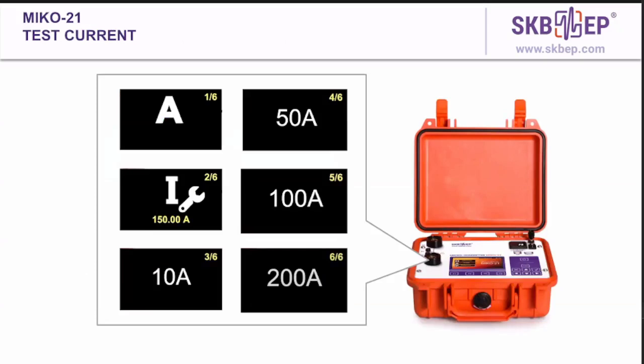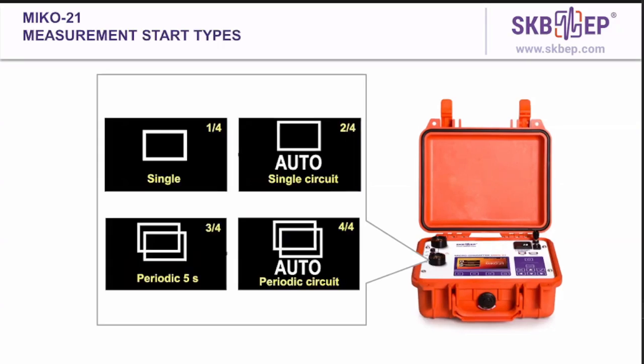In the settings, here it's about the adjustable amperage mode. In the settings, you can choose the current you want. First of all, you can set the automatic mode for selecting the test amperage. You can set it manually in the range from 1 up to 200 ampere with a step of 1 ampere. And you can also select from a number of specified values. It can be 10 ampere, 50 ampere, 100 and 200 ampere.